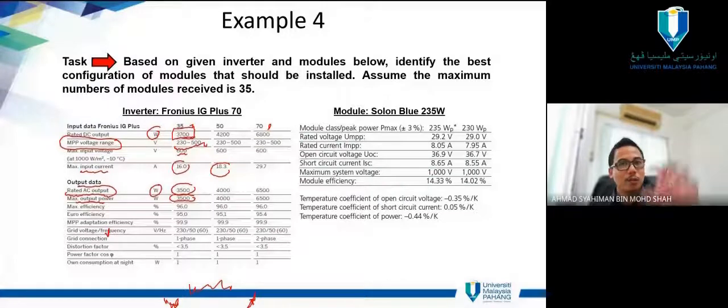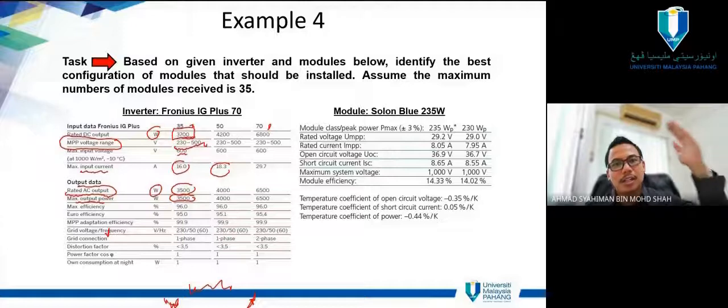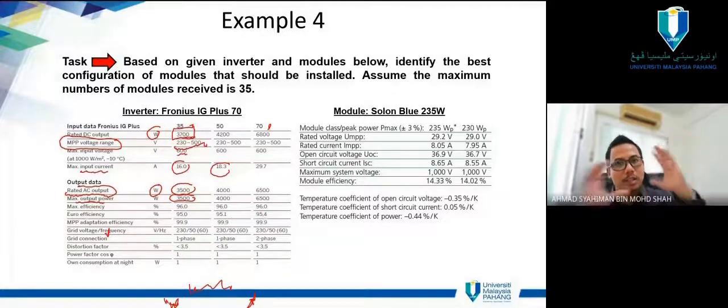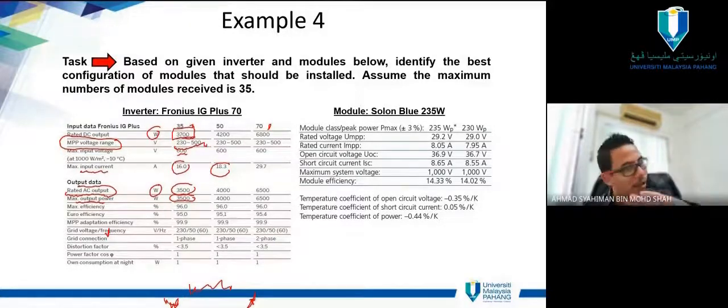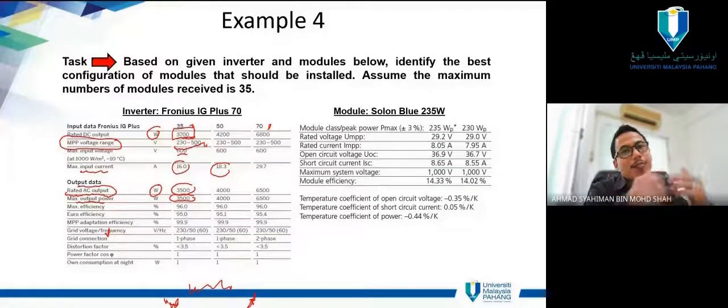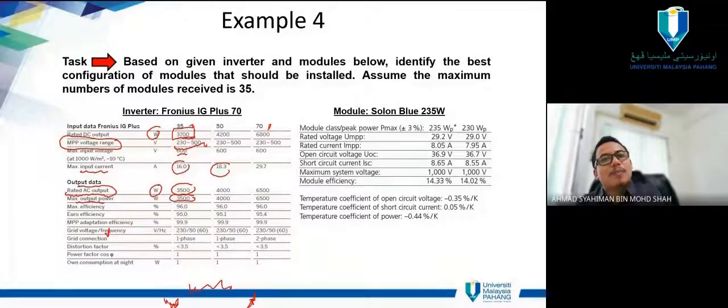Like I told you, we have the factors, degradation factors: FMM, FSTEM, FDIRT, FDC drop, all the factors that degrade the system. That one, you need to consider. Even though the megawatt of your module is 30 megawatt, you won't get it, especially when it rains. So the target must be oversized. DC tu mesti lebih lagi. But the inverter must comply with the same target.